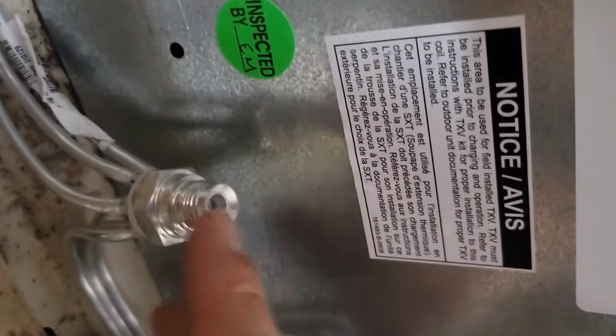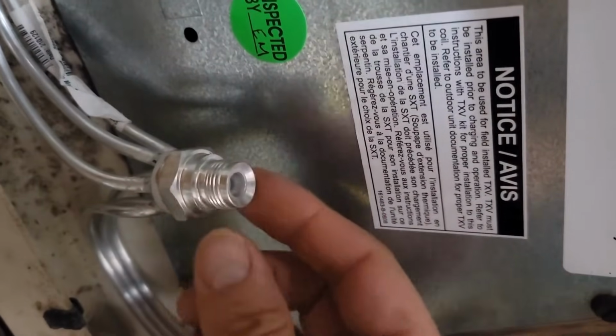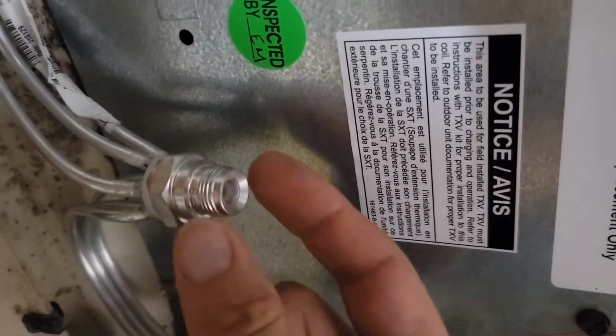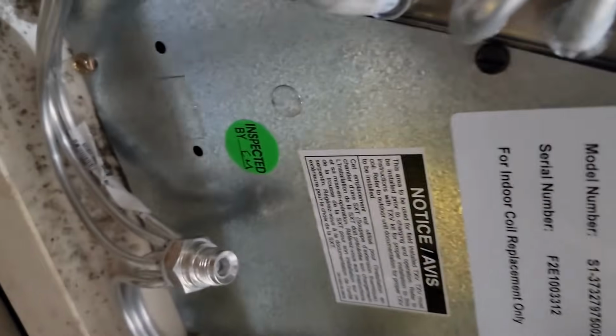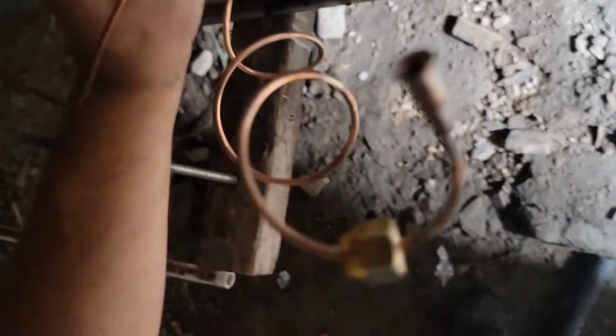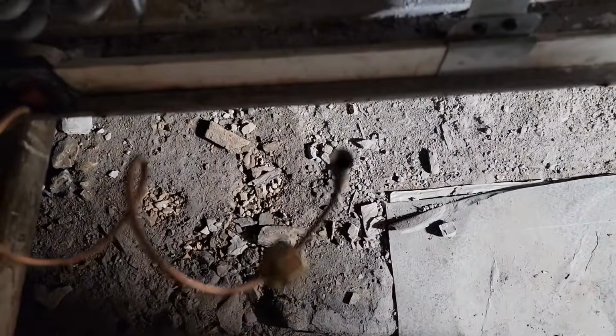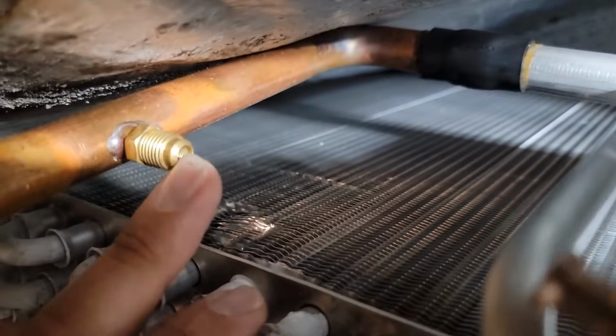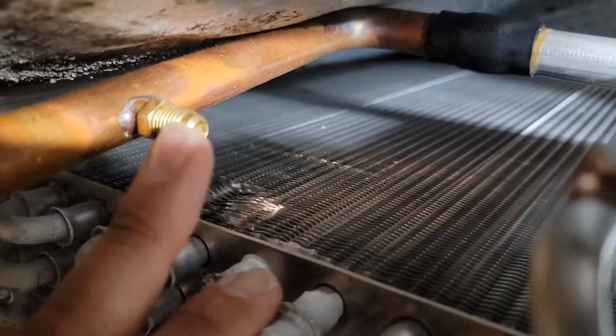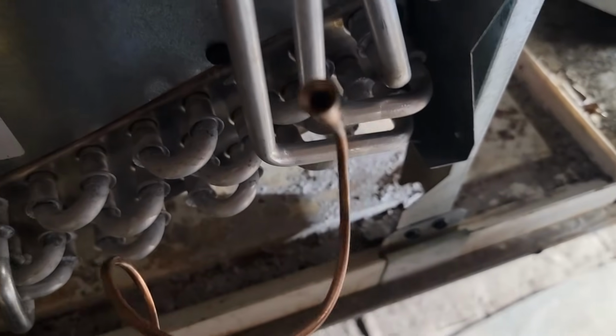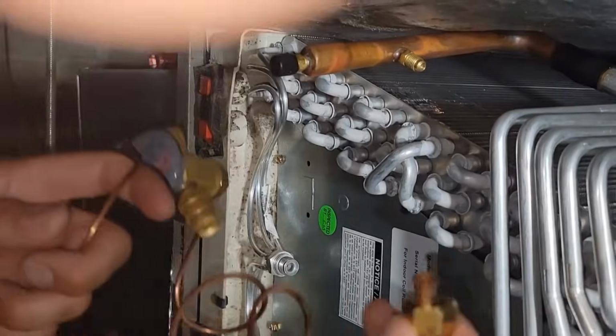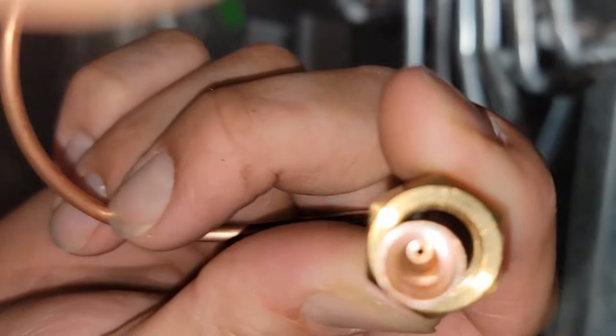Tip for installing the TXV: make sure that you hand tighten the connection to this aluminum piece right here, and after you hand tighten, just do a quarter turn past hand tight. It doesn't need a gasket because it's beveled right here. And then this port, you'll need to look inside this port here and see if there is a little plunger. And if it has a plunger, then you have to have a valve stem in here. And if it doesn't have a plunger and it's open, then you'll just connect it. Okay, now this one doesn't have a plunger in the end, so we're just gonna connect it right here, okay? All right, no plunger here, it's just open, so yay.